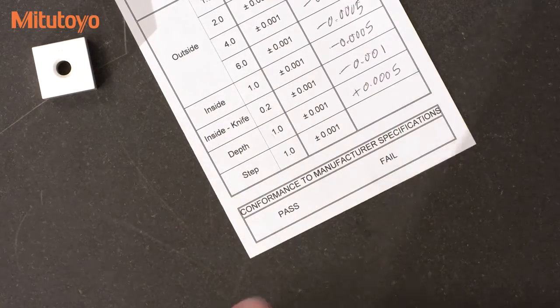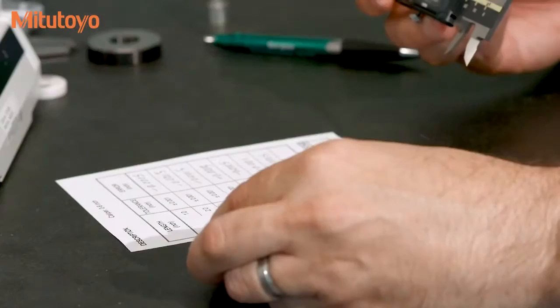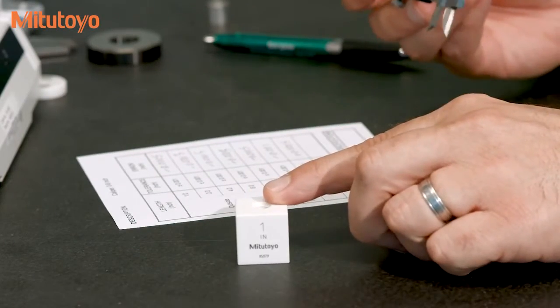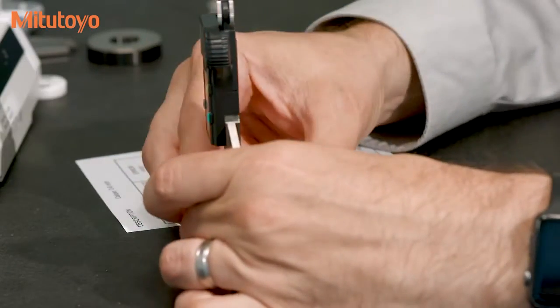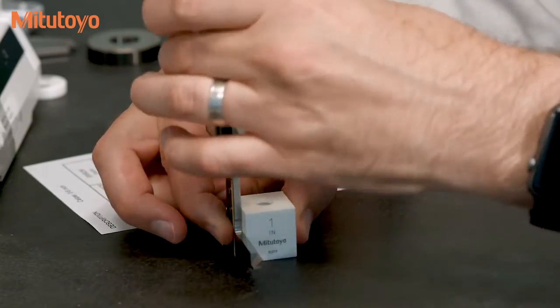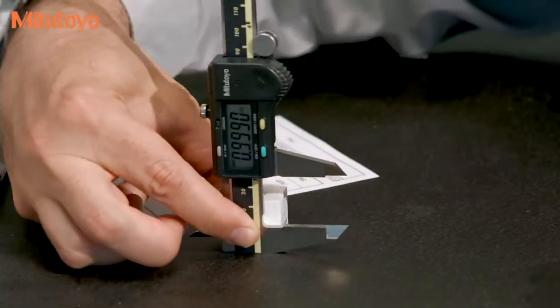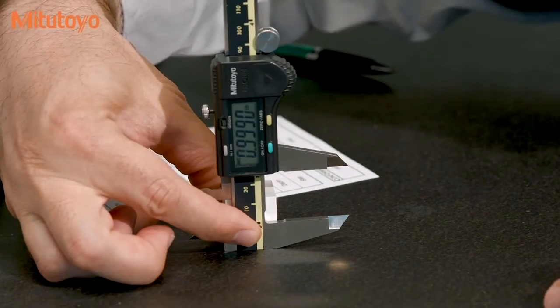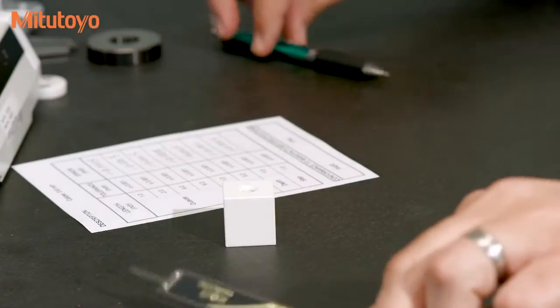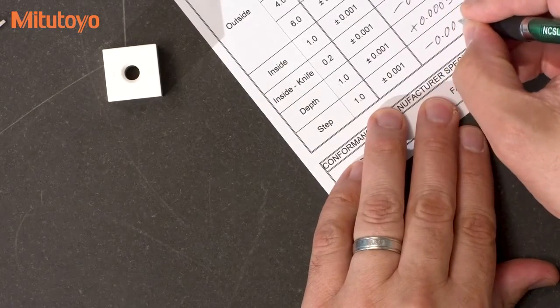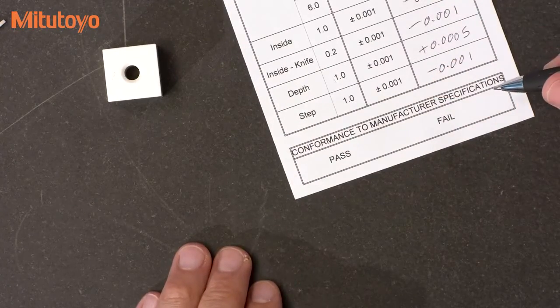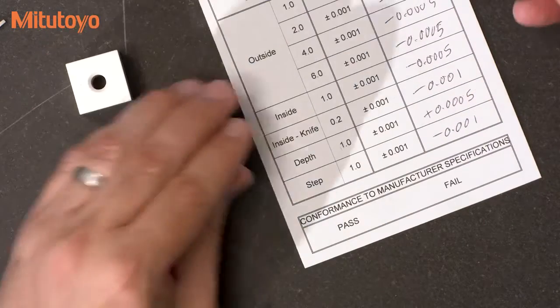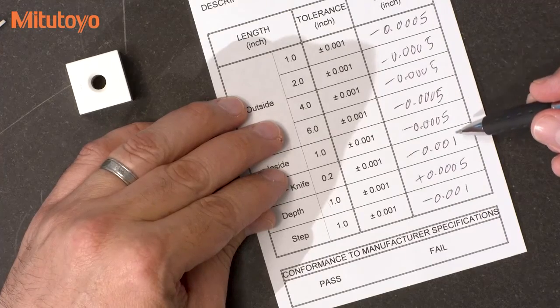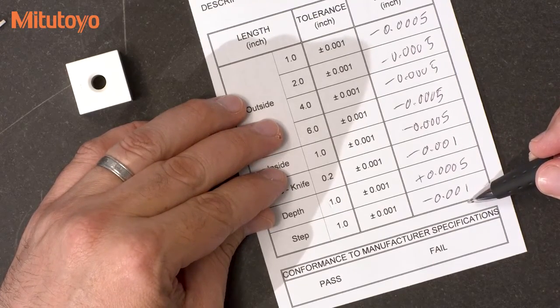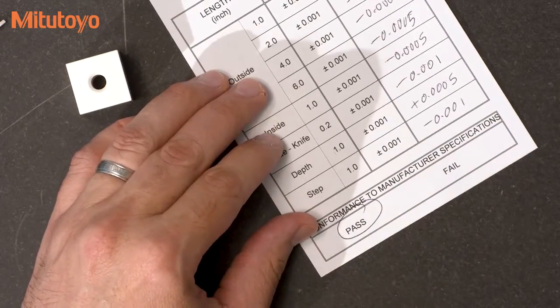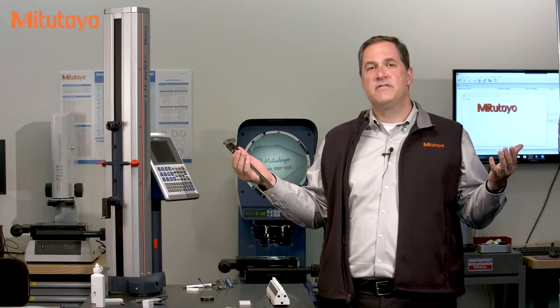Lastly, we do the step measurements. Again, a square gauge block works well. We'll use the same 1-inch gauge block. We can hold the caliper against the block and simply take our reading. Looks like the error is minus a thousandth of an inch. So we'll write that down. So this completes the calibration. All the errors here are within the plus or minus 1/1000th of an inch specification. So it looks like this caliper is in tolerance. And that's the calibration of calipers.